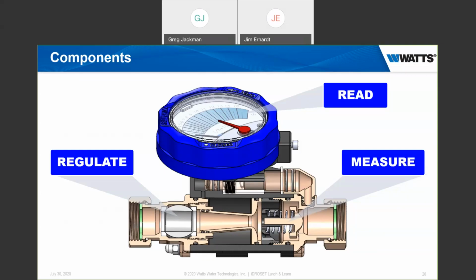But it's essentially a fixed orifice valve that's working on a Venturi, but it also is sort of like a variable orifice, in that the spring check valve mechanism on the right is going to move depending on the flow rate. So if someone asks, is it a variable orifice or a fixed orifice? It's kind of both. It's a unique design that's going to be measuring the flow directly and give you the readout on the gauge. So that's sort of what the inside of the valve looks like, and fundamentally what it's doing.